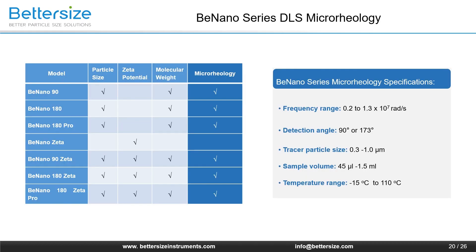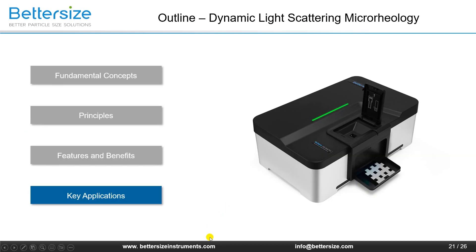DLS microrheology is available on the BeNano series instruments except the BeNano Zeta. Specifications include: frequency range from 0.2 to 13 million radians per second, detection angle of 90 or 173 degrees, tracer particle size from 0.3 to 1 micrometer, sample volume from 45 microliters to 1.5 milliliters, and temperature range from minus 15 to 110 degrees Celsius.